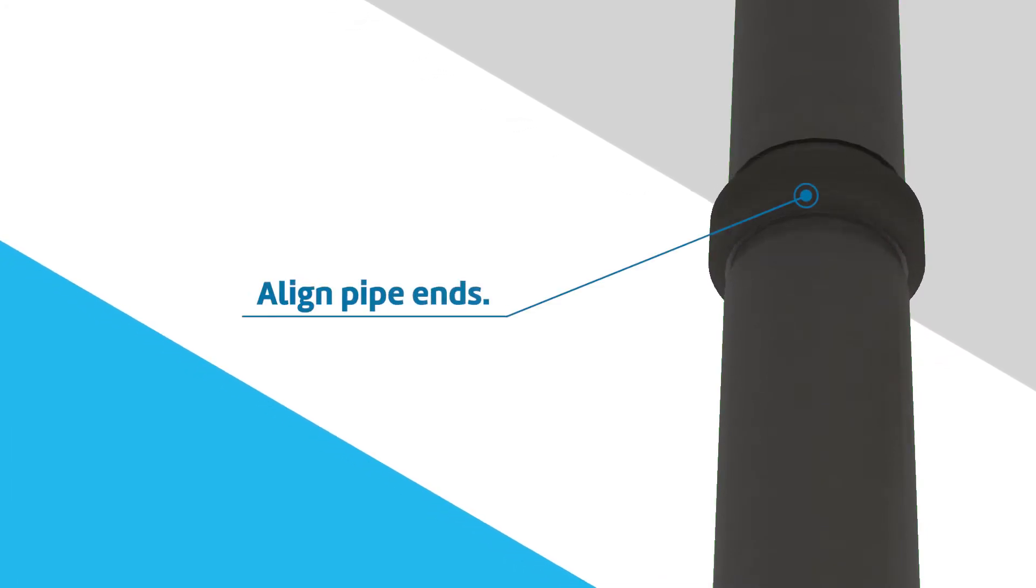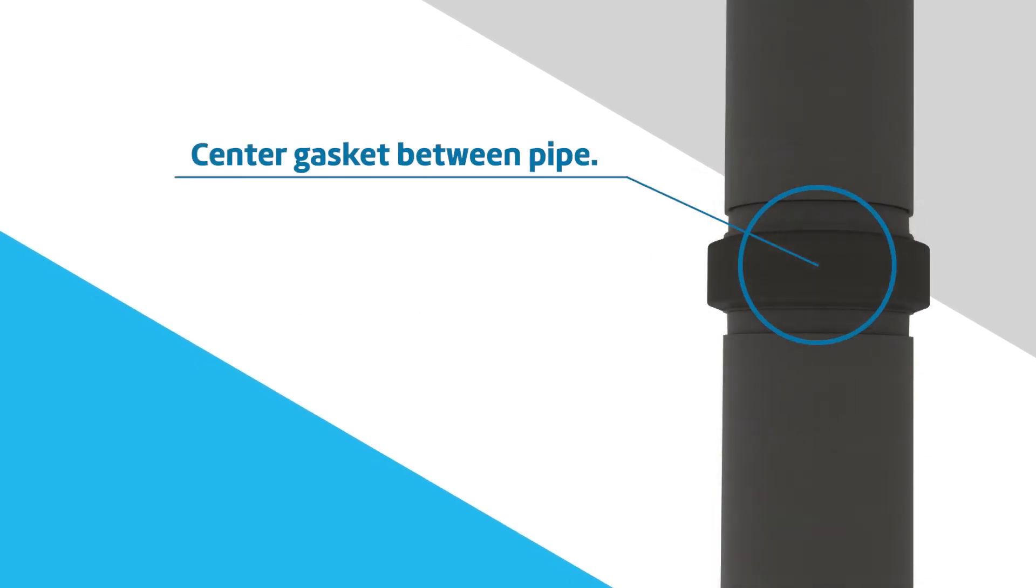Align the two pipe ends and pull the gasket into position, centering it between the grooves on each pipe. The gasket should not extend into the groove on either pipe.